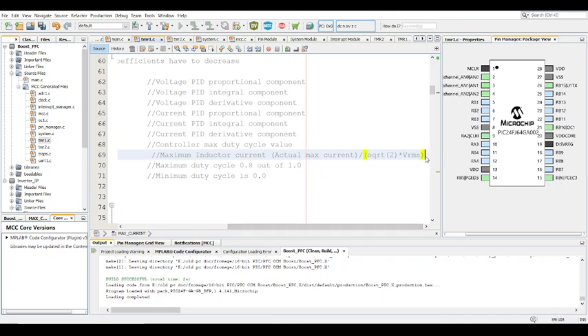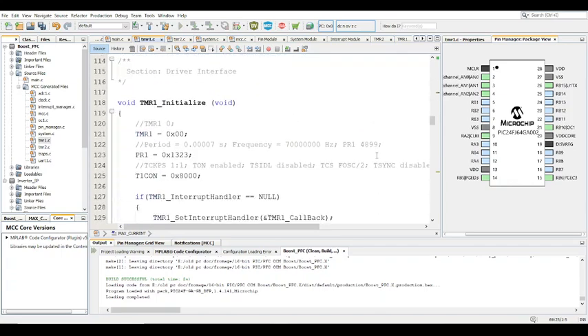This highlighted part is the V peak. You take the square root multiplied by VRMS. So VRMS is 230 volts, multiplied by root 2. Then it's the actual max current divided by 230 multiplied by root 2, and that's how you get this particular value. I think this is equivalent to 20 amps.